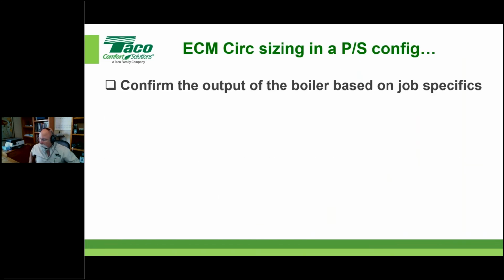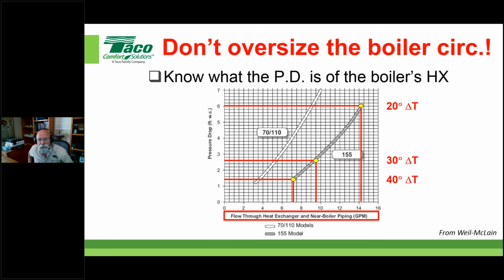So Rick, let me just clarify. You're saying that the boiler pump for a 155,000 BTU ModCon boiler, if my design delta T across that boiler's heat exchanger is 40 degrees, that boiler pump only has to be able to provide a shade over 7 gallons a minute at a little bit less than a 1.5 foot of head pressure differential. Is that right? That's what that's saying. And you've got to always remember this, and only at a design condition. Mm-hmm. Okay. We can see how really easy it is to oversize a boiler pump now, to the point where it is to the detriment of that boiler's operation. Absolutely.